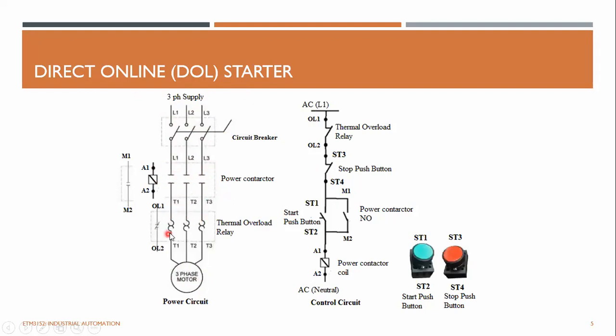And you have a thermal overload relay in the bottom. So if the current is too high, this will disconnect. At the same time, there's an overload auxiliary contact, which means an indication of overload, which can be wired to a PLC to display. If an overload happens in the motor, you can display that. So you have to wire it to a PLC, or you can use it for any other purpose. Which means if this contact is open, this normally closed contact will open, so you can use it for monitoring.